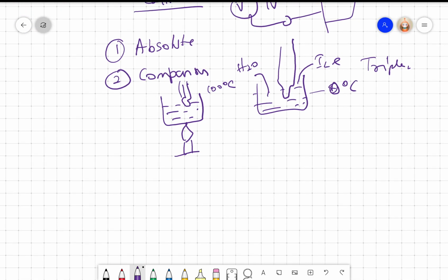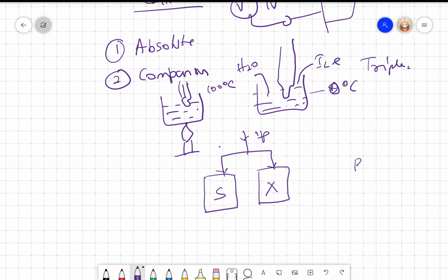But many times that may not be possible. So what we do is have a standard sensor and an unknown sensor, and give the same input to both. Whatever the unknown sensor reads, I call X, that's the measured value. The standard sensor reads S. Then X minus S divided by S into 100 would be the percentage error in X.